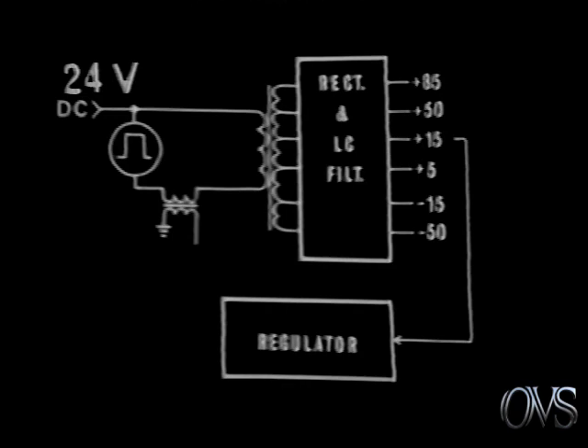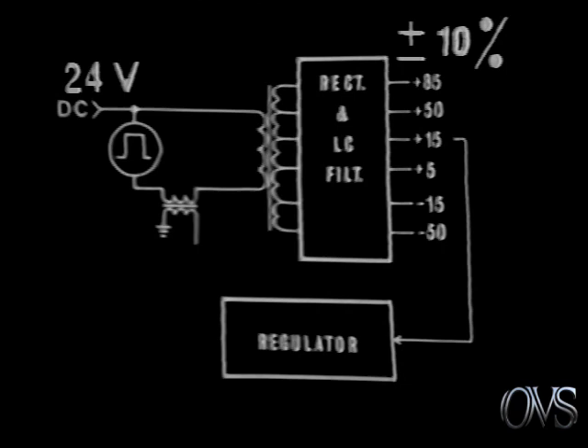If all outputs are out of tolerance and cannot be adjusted, the trouble can be isolated to either the regulator or the oscillator circuit. First, disconnect the regulator. Then, using a variac in the AC line input, reduce the DC at the converter input to 24 volts. A properly operating oscillator and rectifier will provide DC outputs within 10% of normal even without the regulator. With this setup, all outputs within 10% of normal indicate the trouble's in the regulator.